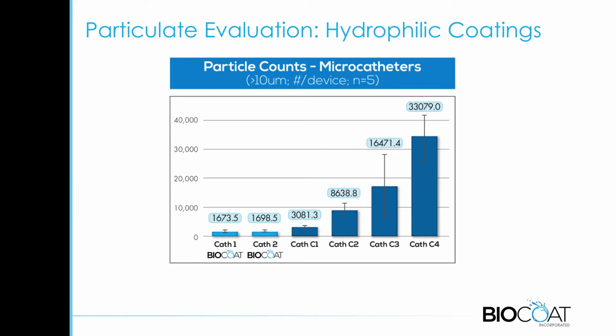Looking at the particulate evaluation for these hydrophilic coatings, we're looking at it two different ways. One is the total particle counts from these microcatheters, the number of particles greater than 10 microns for the entire device. You can see a rather dramatic difference between the various coatings. Catheter C4, which didn't have great durability, not terribly surprisingly, has rather high particulate generation. Some of the ones with the Biocoat coatings had very low particulates, and some of the other ones had about twice that. But other ones had rather higher values, 10x higher than some of the best-in-class ones.